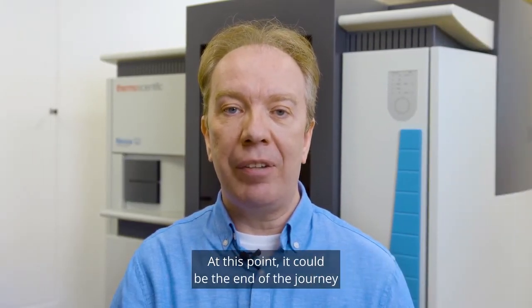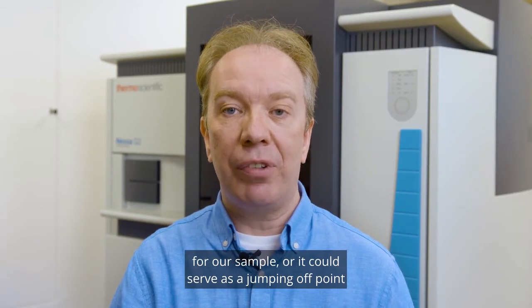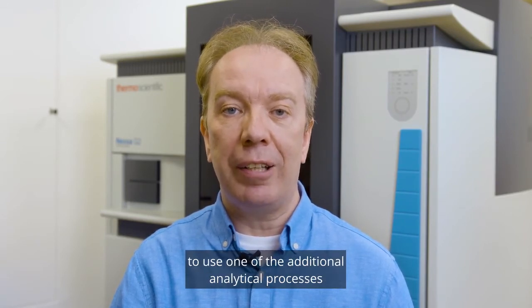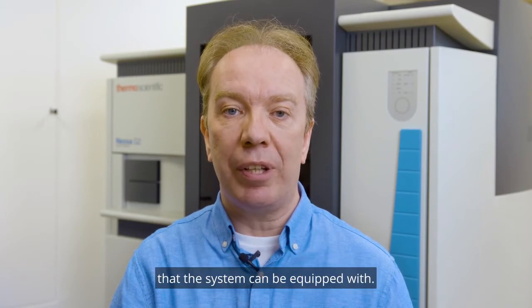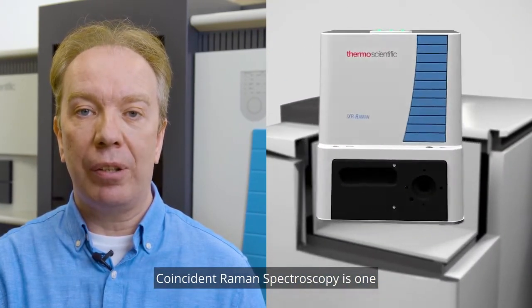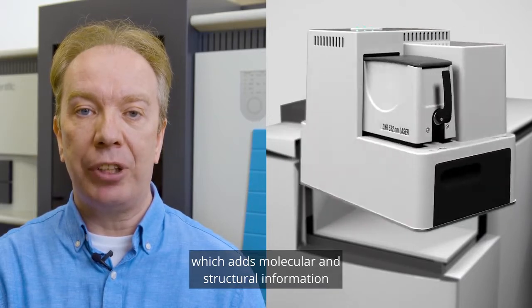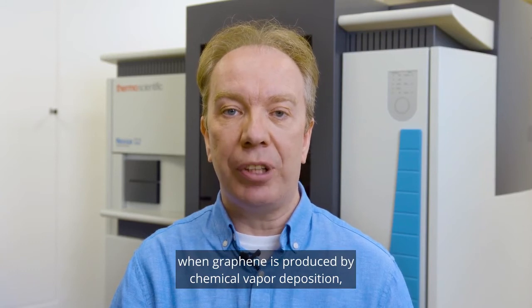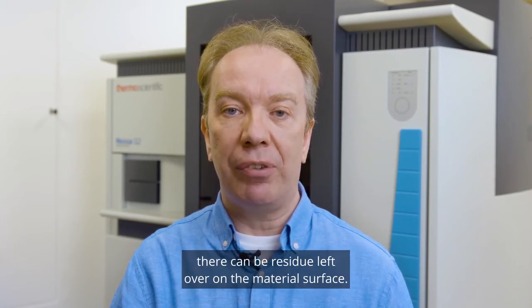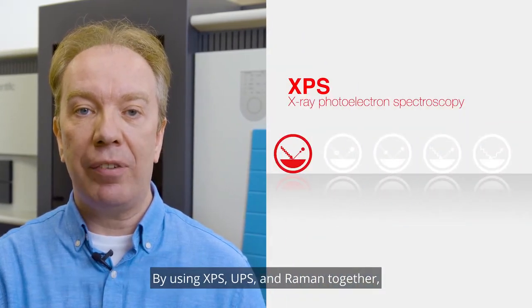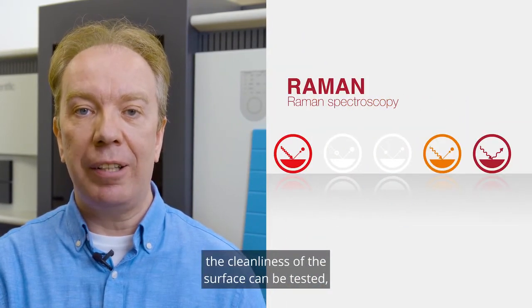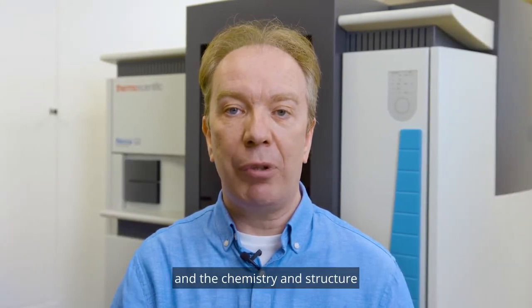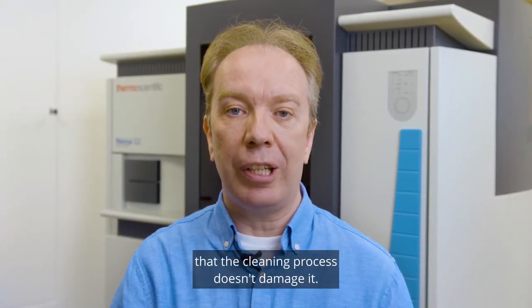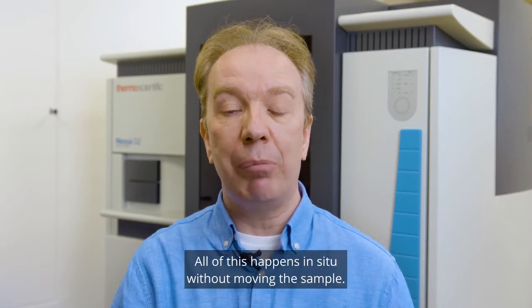At this point, it could be the end of the journey for our sample, or it could serve as a jumping off point to use one of the additional analytical processes that the system can be equipped with. Coincident Raman spectroscopy is one, which adds molecular and structural information to our dataset. As an example, when graphene is produced by chemical vapor deposition, there can be residue left over on the material's surface. By using XPS, UPS, and Raman together, the cleanliness of the surface can be tested, and the chemistry and structure of the film can be monitored to ensure that the cleaning process doesn't damage it. All of this happens in situ, without moving the sample.